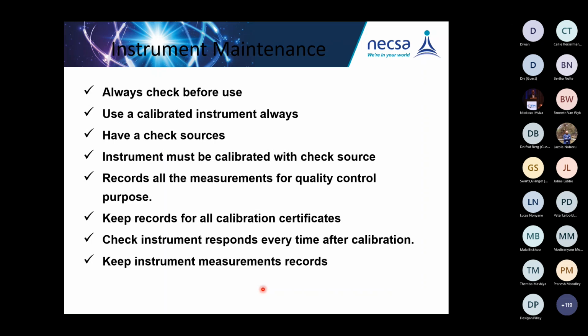And a check source can be made out of any radioactive material which is not a CRM, a certified reference material. And when you have your check source, every time it is calibrated, they will calibrate it against that check source measurement. They will present those measurement results. Anytime you take your instrument to the field, you place it against the check source to see whether it is still reproducing your upper limit and lower limit for the check source. Is it still within the range? If it's still within the range, that gives you the confidence, and you can take your instrument into the field with a happy smile.